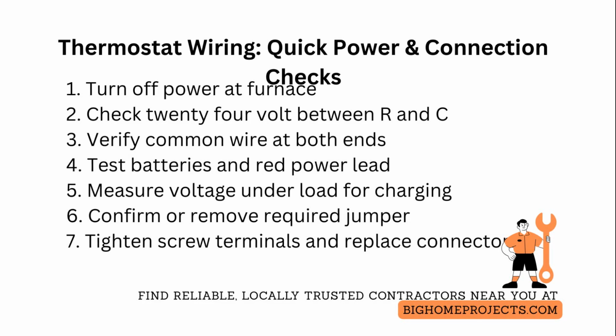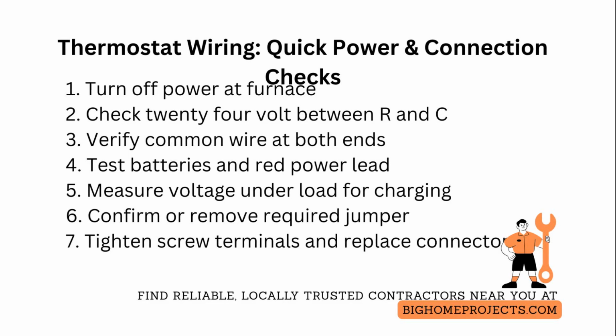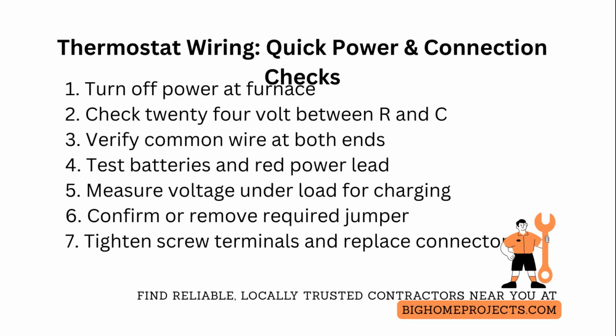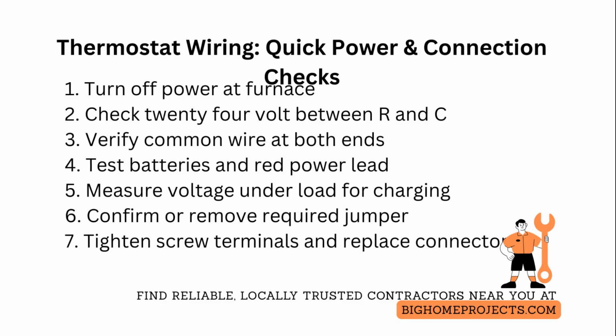Finally, if wiring and voltage check out but the display remains dead, swap in a known good thermostat or bench test the control board to isolate whether the issue is the thermostat unit or the home wiring and transformer.